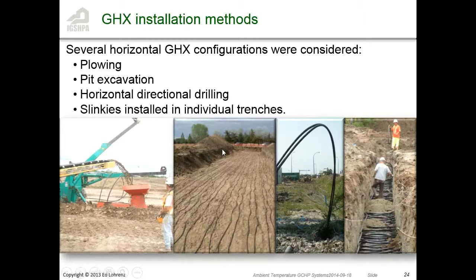We basically designed a ground heat exchanger where you can do this, or this, or this—take your pick, whichever is most cost effective. There's no reason you have to stick with a specific type of ground heat exchanger configuration. It can sometimes be more cost effective. You've got a school, for example, with enough land area to do a horizontal loop. It's amazing how that can sharpen the pencil of drillers in the area. There's no reason you can't design a vertical ground loop if they want to do that—knock yourselves out, here's how much drilling you'll need. You want to do horizontal? You can do it that way, whatever way you find most cost effective. That opens it up to more contractors that can bid on the project and gets the pricing a lot more competitive.